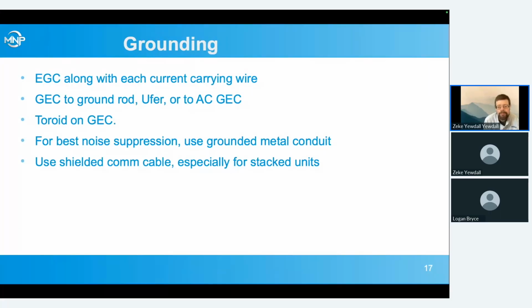Grounding, we talked a bit about a bunch of this already, but we want to have that toroid on our grounding electrode conductor, whether that's going to the ground rod, UFER, or back to the AC grounding electrode conductor. We want our equipment grounding conductor run with all of our different current carrying wires. This is just standard electrical code. If we're concerned about noise suppression, in addition to the toroids in there, we want to use grounded metal conduit. And we have had some people, ham radio operators, put extra toroids on a lot more wires in there to really get it to the level of noise suppression that they wanted.